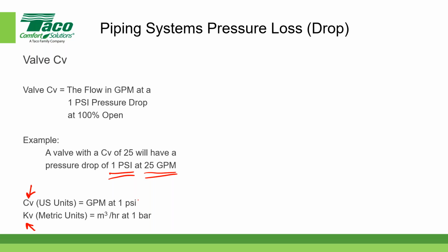And so again, if we had a valve with a CV equal to 25, that means it will allow 25 gallons per minute at a 1 PSI pressure drop. If it's a KV, it would be metric, and it would be cubic meters per hour at 1 bar, and that's the definition.